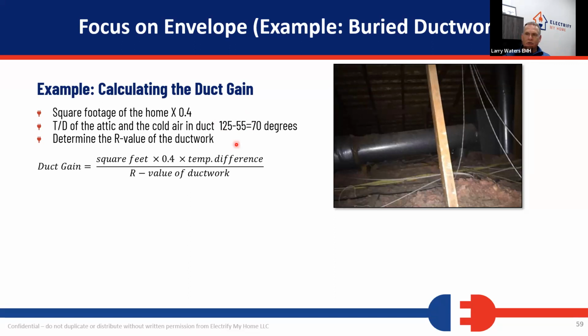So these are pretty conservative numbers. If we take a 125-degree attic, we have 55-degree air coming through the register, or coming through into the ductwork. That's a 70-degree temperature differential. And then we determine the R value of the ductwork. Real easy.